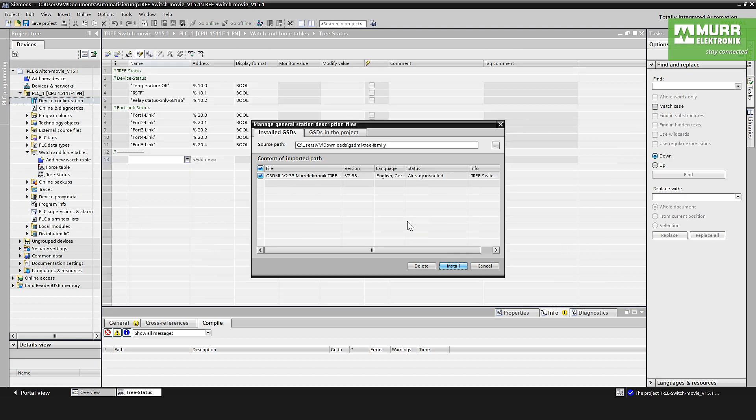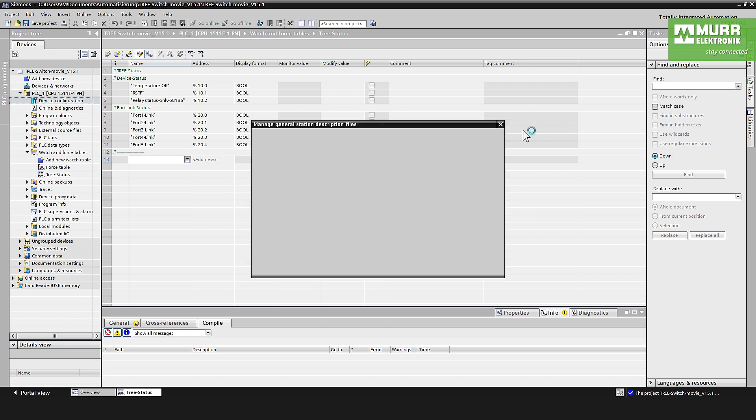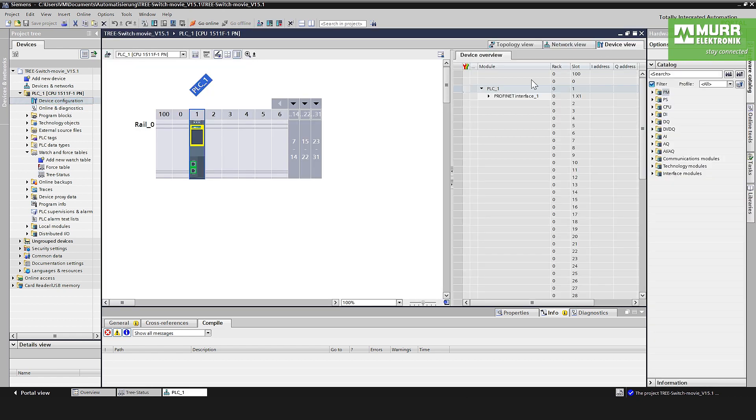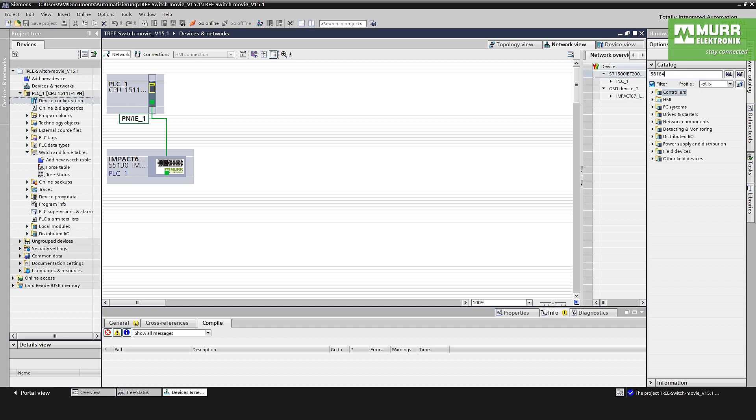After installing, now you'll find the GSD file or the information of this device on the hardware catalog. To find the switch is very easy. You go here to the search area on the catalog, put our article number from the device, in this case 58184, press enter, and TIA Portal found automatically the location of the installed GSDML file.